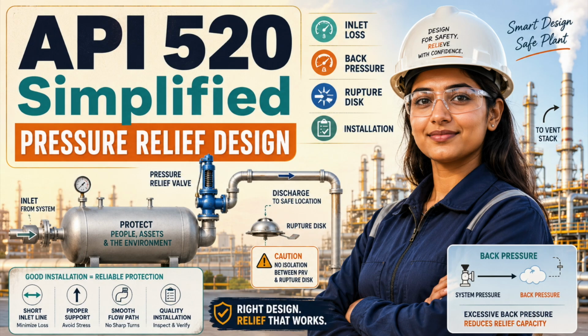You must separate two engineering problems clearly. First, determine how much fluid must be relieved. Second, determine what device and flow area can safely relieve it. The first is process system analysis. The second is relief device engineering. A perfect valve sizing calculation cannot rescue a badly defined overpressure case.